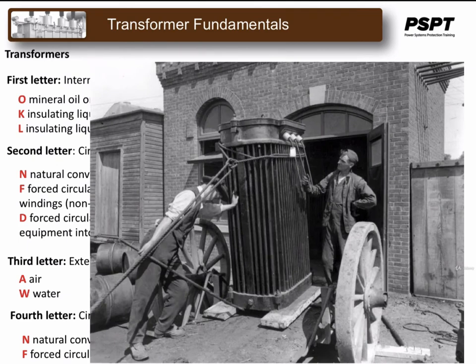Unfortunately, a lot of transformers that were built and are still in service today, prior to the IEEE adopting its standard of a 4-letter designation, the ratings may not be found in their full 4-letter designation. In these cases, you will have to use your ingenuity and a little imagination to interpret the cooling ratings, as you will see in the following examples.